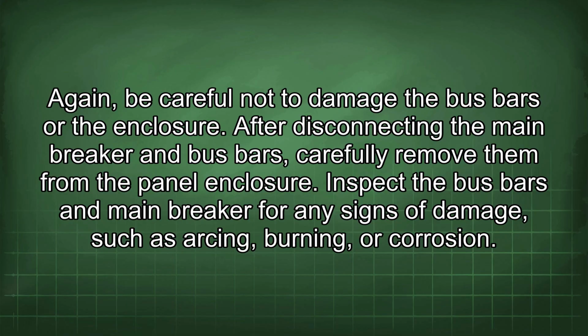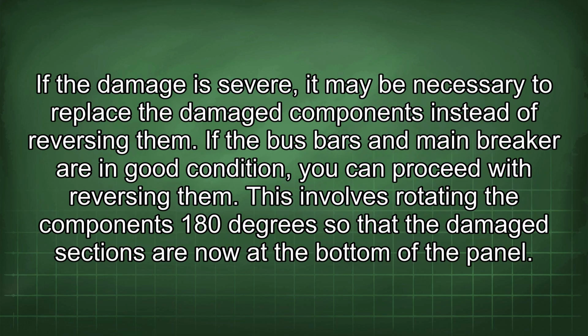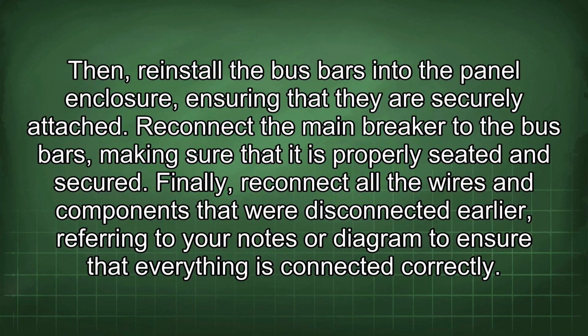Inspect the bus bars and main breaker for any signs of damage, such as arcing, burning, or corrosion. If the damage is severe, it may be necessary to replace the damaged components instead of reversing them. If the bus bars and main breaker are in good condition, you can proceed with reversing them. This involves rotating the components 180 degrees so that the damaged sections are now at the bottom of the panel. Then, reinstall the bus bars into the panel enclosure, ensuring that they are securely attached. Reconnect the main breaker to the bus bars, making sure that it is properly seated and secured.